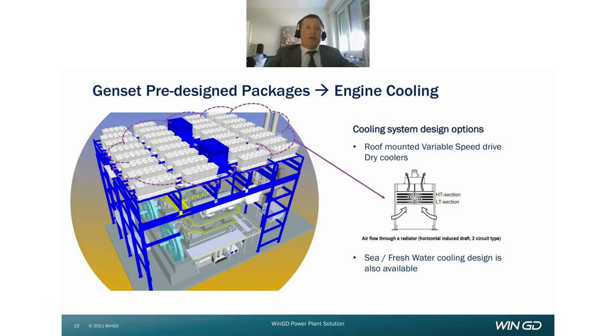As I mentioned before, the genset cooling system has been designed to be suitable for a closed-loop circuit. In this particular application, a set of V-shaped dry coolers are located on the genset module roof to limit the overall plant footprint. The dry coolers are equipped with variable speed fans. The cooling airflow is automatically adjusted based on the ambient temperature. This control logic allows saving a fair amount of energy drawn by the radiator across the year. The control and drives of each dry cooler fan are implemented by the dry cooler panel, while the generator control panel provides the enabling commands and continuously monitors the status of each fan.